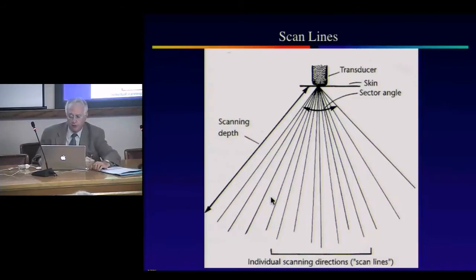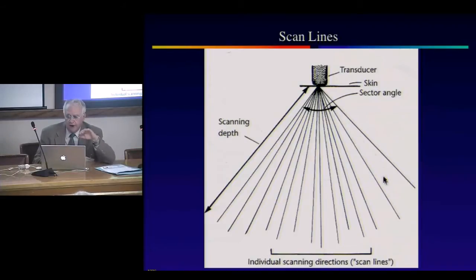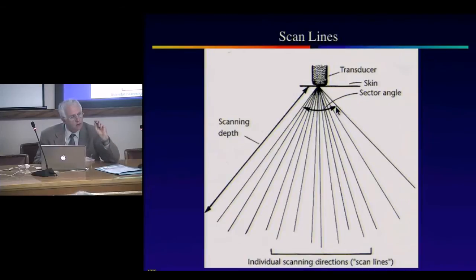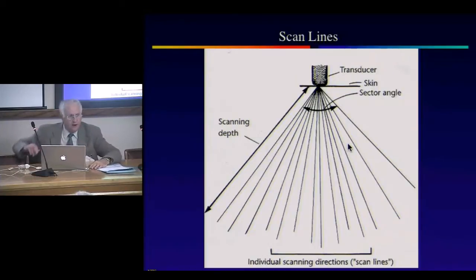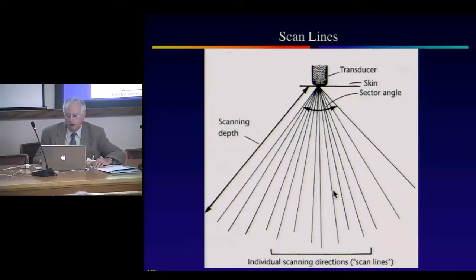Near field length is subject to mathematical equations shown on the board. When steering the beam, we initially steered along scan lines. In old ultrasound machines, these lines would diverge further away. Techniques such as dithering — pretending there is another signal between two real ones — and increasing the number of scan lines address this. Old probes had 16 elements; modern ones have 512 elements, greatly increasing scan line density and lateral resolution.